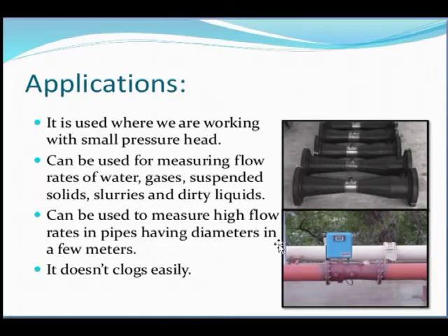Then the applications. Venturimeters are used when we are working with a smaller pressure head. Also, they can be used for measuring the flow rates of water, gases, suspended solids, slurries, and dirty liquids. The venturimeter doesn't clog easily and can be used to measure high flow rates in pipes having diameters of a few meters. These are the applications of the venturimeter.